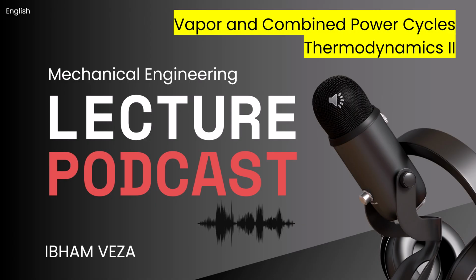Exactly. Instead of just venting that hot exhaust to the atmosphere, which wastes all that high-temperature energy, a combined cycle uses it as the heat source for the steam cycle's boiler. Ah, so the gas turbine's waste heat becomes the steam turbine's input heat. It's like cogeneration, but between two different power cycles. Precisely. The steam cycle acts as the bottoming cycle, recovering heat from the topping gas turbine cycle. It's a perfect marriage because their temperature ranges complement each other so well. And this significantly boosts overall efficiency.